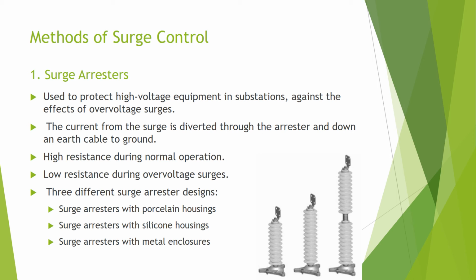Effective overvoltage protection requires different surge arrestor types to be used according to the particular application. There are 3 main types: surge arresters with porcelain housing, surge arresters with silicone housing, and surge arresters with metal enclosures. During normal operation, a surge arrestor should have no negative effect on the power system. Moreover, the arrestor must be able to withstand typical surges without incurring any damage.